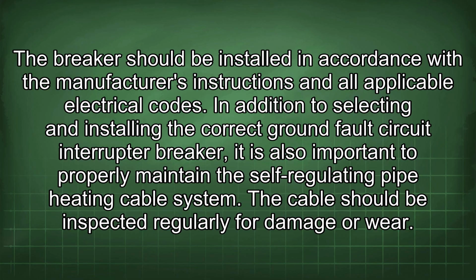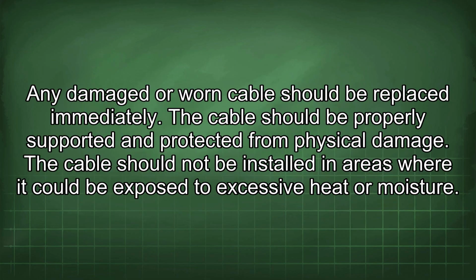In addition to selecting and installing the correct ground fault circuit interrupter breaker, it is also important to properly maintain the self-regulating pipe heating cable system. The cable should be inspected regularly for damage or wear. Any damaged or worn cable should be replaced immediately. The cable should be properly supported and protected from physical damage. The cable should not be installed in areas where it could be exposed to excessive heat or moisture.